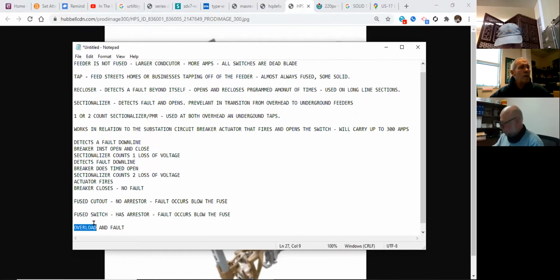So that's 15 amps. It's going to 17, 18, 19, 20 - that's overload. All right, what's the difference between that and a fault? Hold on. Fault's like a cutout, ain't it? Well, what is a fault itself? Very intense - trying to get those, all right? Yeah, very high amps.